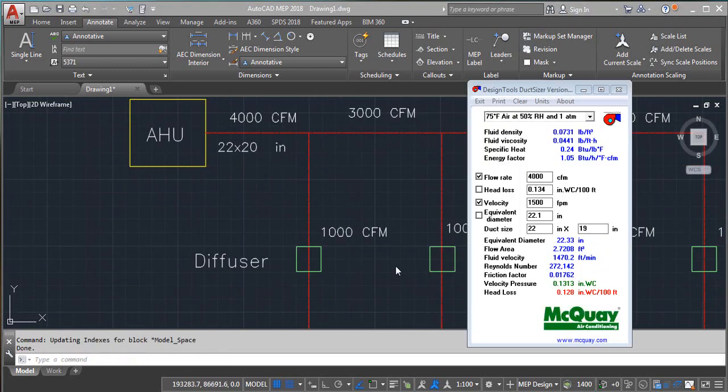Now the sizing of the branch duct. The branch duct needs 1000 CFM as flow rate, and we already calculated the head loss, which is 0.134. Put a check mark on the head loss and enter the value. And now enter the value of the flow rate, which is 1000. Now the equivalent diameter, if it will be a round duct, is 13.1 inches, and if it will be a rectangular duct, it will be 22 by 7 inches.